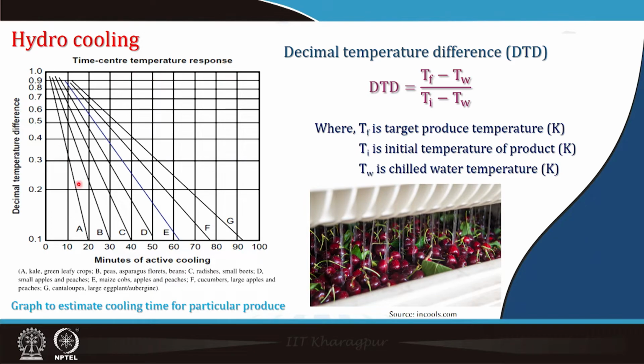From this graph, these lines represent various commodities. Once you calculate the DTD from this equation, DTD equals TF minus TW divided by TI minus TW, where TF is the target product temperature, TI is the initial temperature of the product, and TW is the temperature of the chilled water.